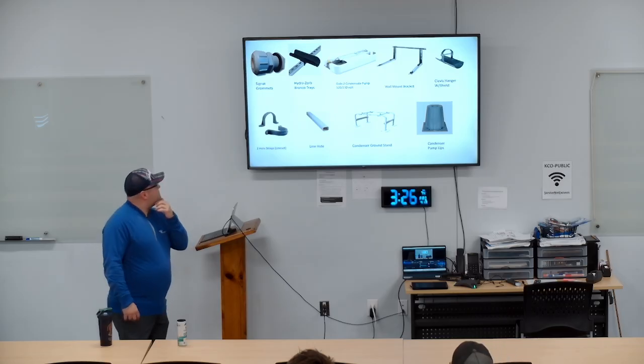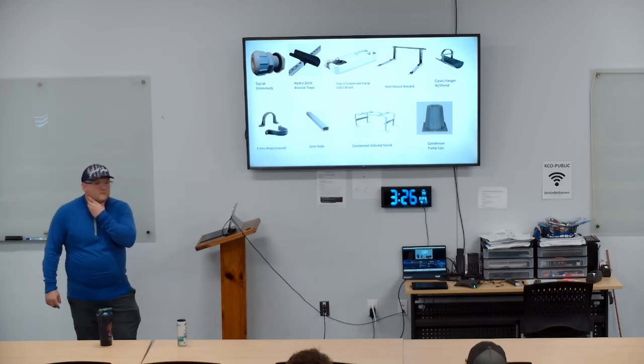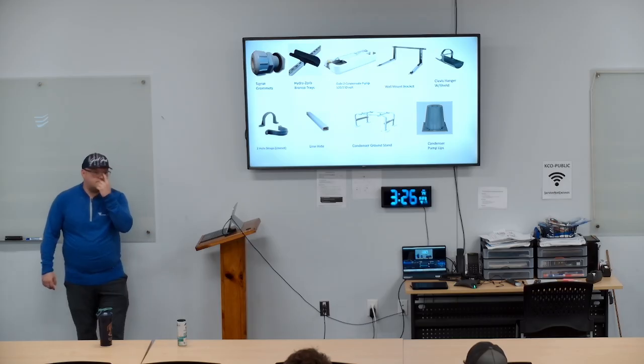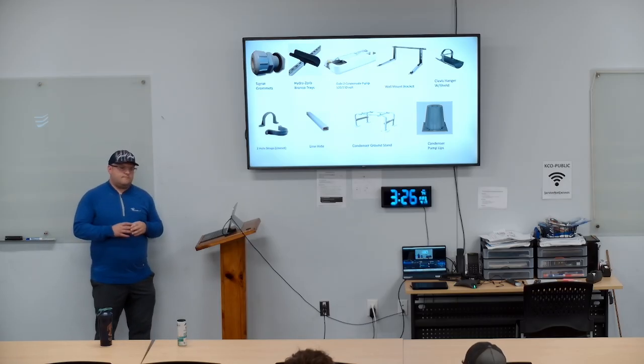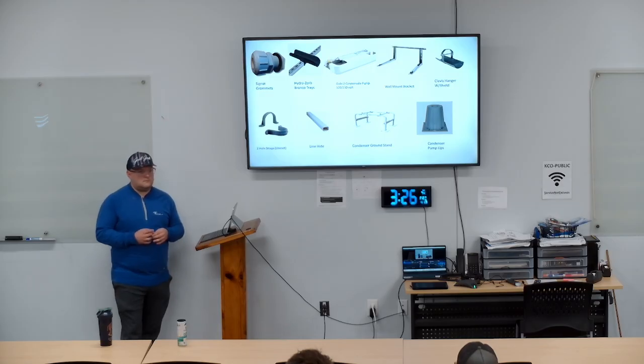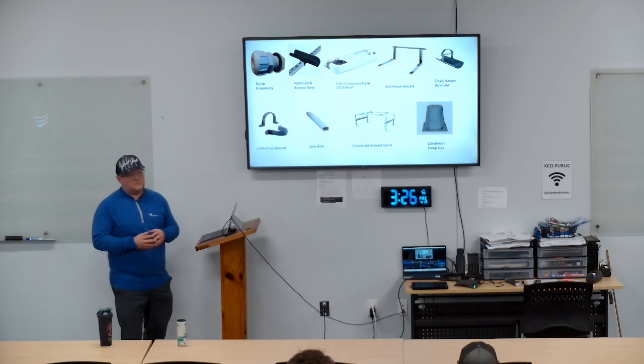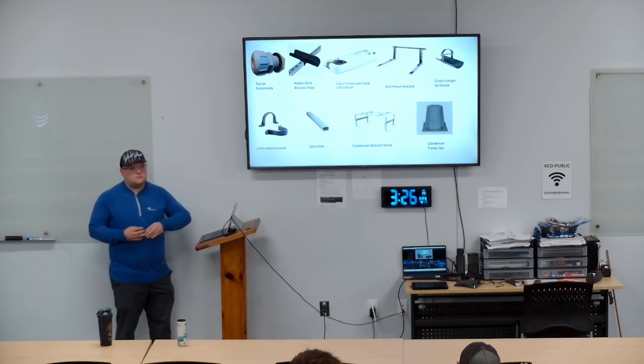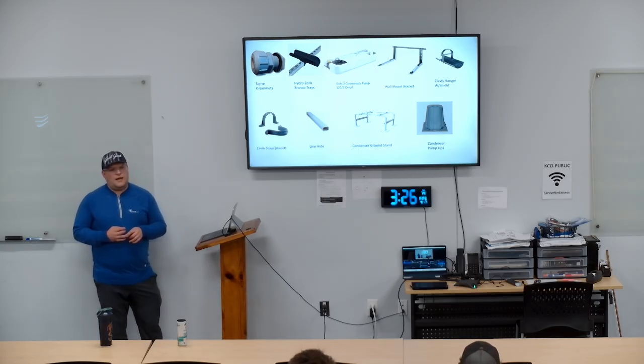Another thing with those Gobi pumps, they come with that little green piece that looks like a check valve. It is not. I think some guys do get confused and think that it is a check valve. Also, it says very clearly in the instructions that it is to be at the highest point in your run. Sometimes I see them 6 inches away from the pump, and they're dripping. The Aspen pumps say to have it 6 feet away from the pump. Again, that goes back to when you do the condensate pumps, read the IOs, read the manuals.